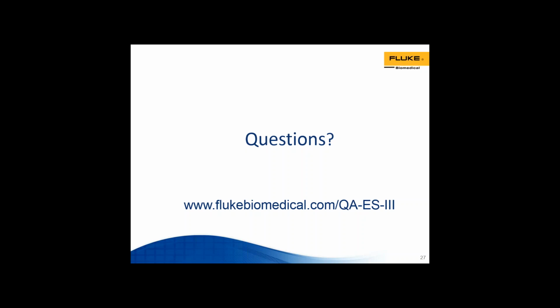Yes, absolutely. I'm sure Jerry would like to chime in here as well because we feel passionately about this one. So yes, the PM maintenance schedule cannot be changed, and the procedure has a given number of steps. But what you can do is condense the amount of time it takes to perform it by automating the device. As many of our end users might already know, manually pushing buttons and driving the analyzer is going to take longer versus having it connected to a PC that automatically makes those connections and drives the analyzer in an automated fashion.